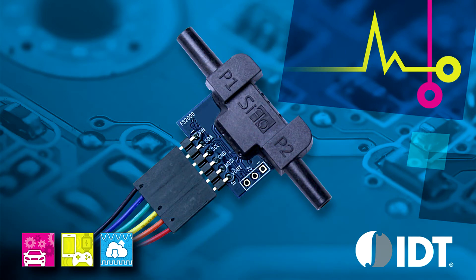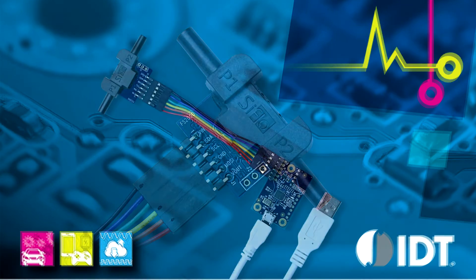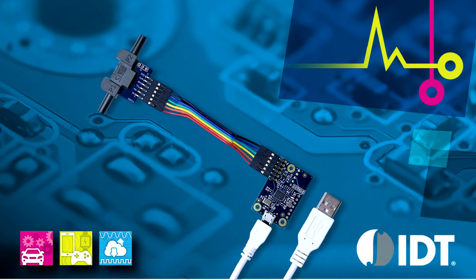The heart of the sensor is a patented hot wire anemometer made out of silicon carbide deposited on a porous silicon substrate. The porous silicon provides a structurally sound base for the sense element without a corresponding thermal loss. The construction makes the flow sensor very robust as there is no fragile membrane.